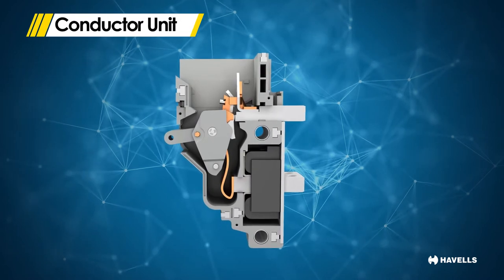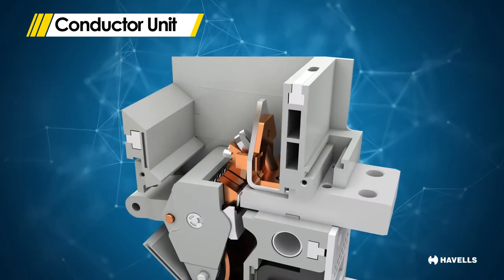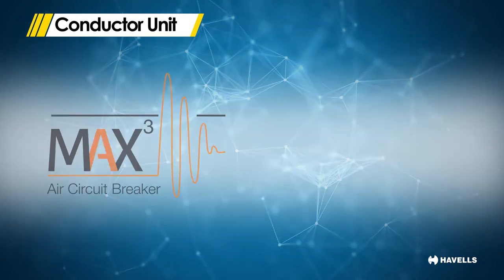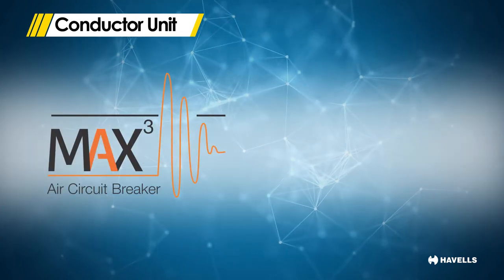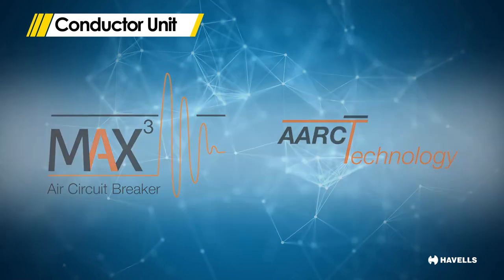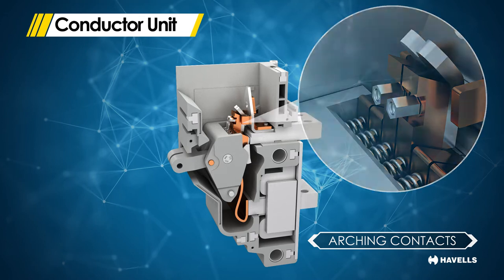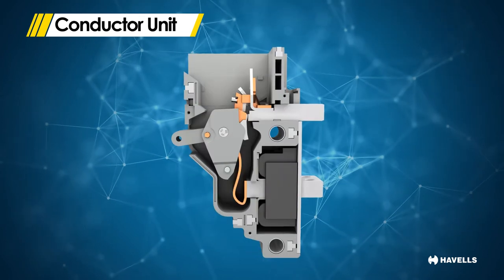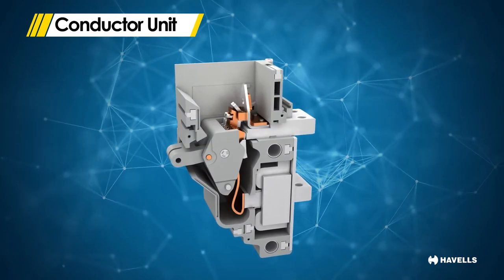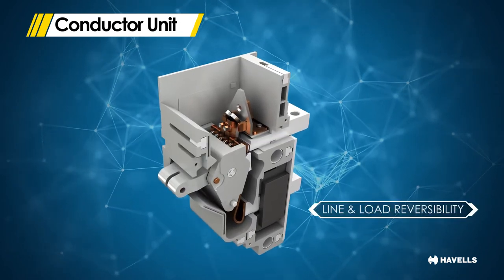The conductor unit consists of the switching and contact mechanism. The conductor unit being modular, the circuit breaker can be configured into a two-pole, three-pole or four-pole breaker. Max3 circuit breakers use the latest unique arc accelerator rapid cooling technology, by which high interrupting capacity is achieved by intensifying the magnetic field around the arcing contacts. The fixed arcing contact support is so designed that it increases the magnetic field around the arcing contacts to assist the fast separation of the contacts, helping achieve higher breaking capacity and line and load reversibility.